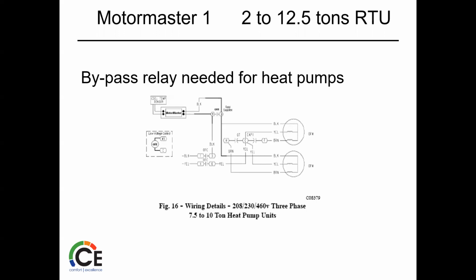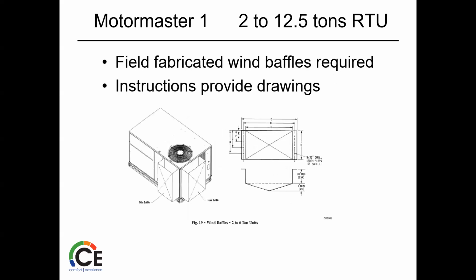At times, again, depending on the models you have, in this case, a 3-phase, 7.5 to 10 ton, there's a bypass relay that's needed. So obviously we're going to wire that in, and sometimes you really have to look at what unit you have, what model is it, what's the tonnage, to really know everything that you're going to need. The relay is for heat pumps, obviously. If it's not a heat pump and it's a gas electric cooling, we don't need it.